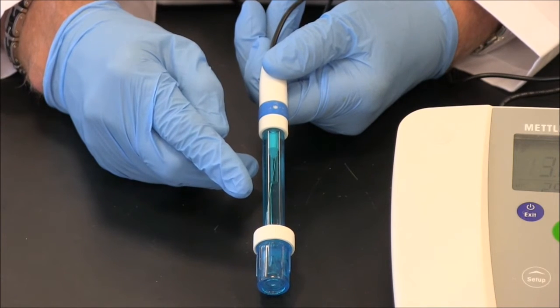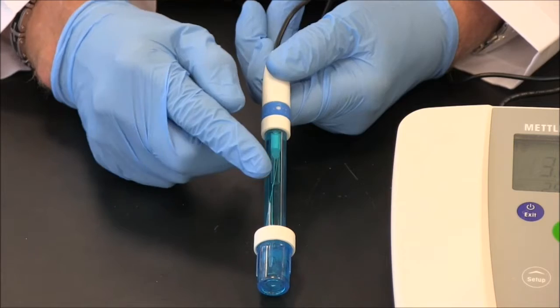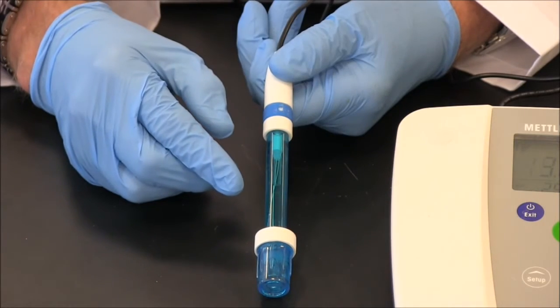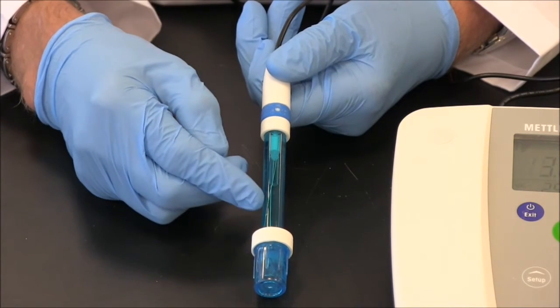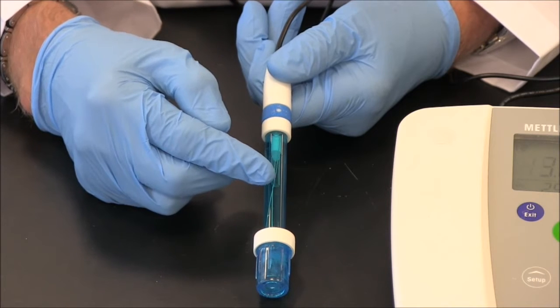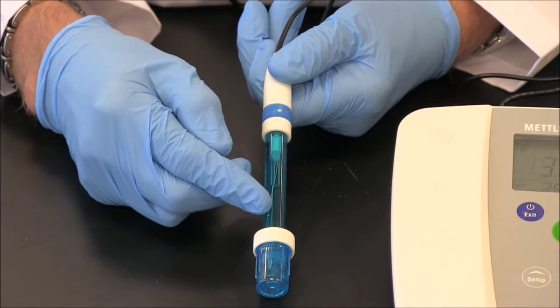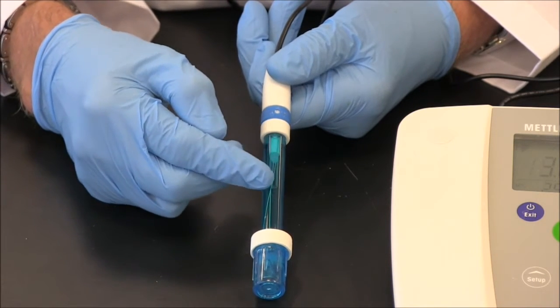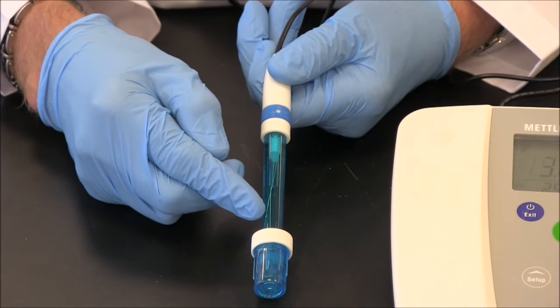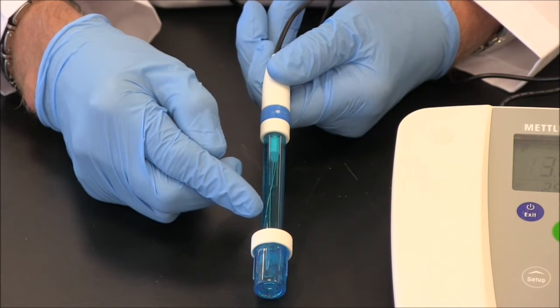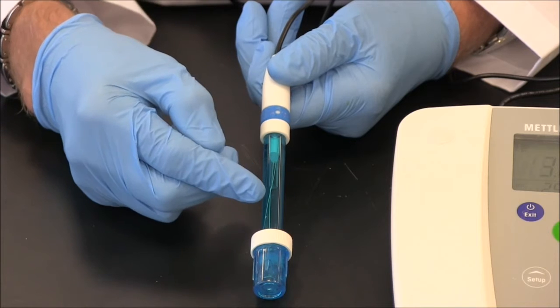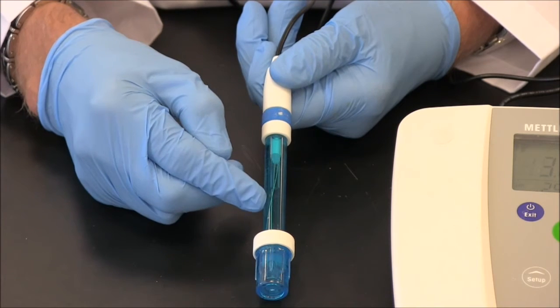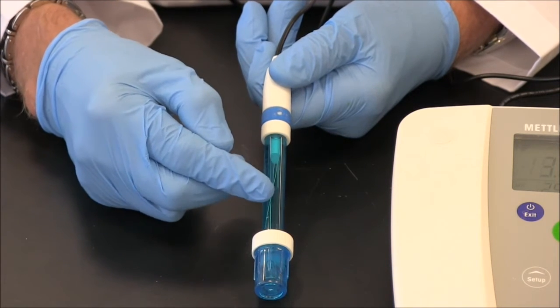This is a combination glass pH electrode, and it's connected to a meter. It forms an electrical circuit. The main parts of the probe are the outer plastic body and the inner glass probe. There are 2 electrodes in the probe, a reference and a measuring electrode. There are 2 reference solutions as well, the KCl solution on the outside and an internal buffer solution.